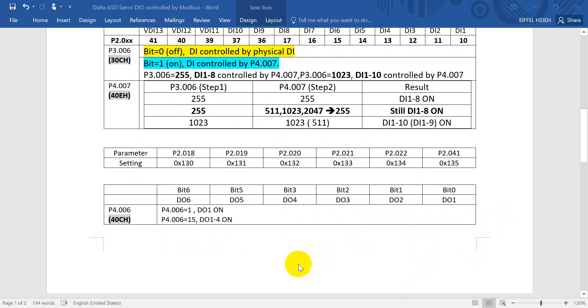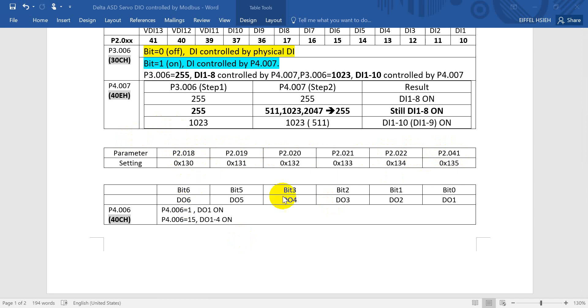Then we come to the digital output setting. You can see digital output 1, digital output 2, digital output 5, and digital output 6 with their corresponding settings. If we define P4-006 equal to 1, that means DO1 is on. And if we define P4-006 equal to 15, then DO1 to DO4 will be on.